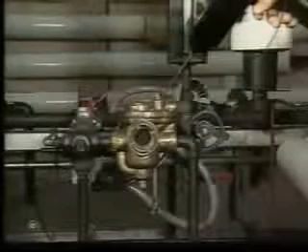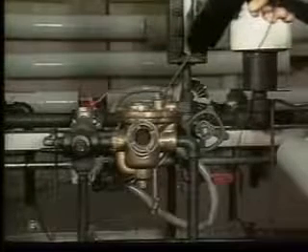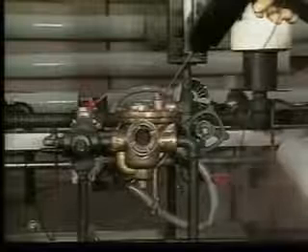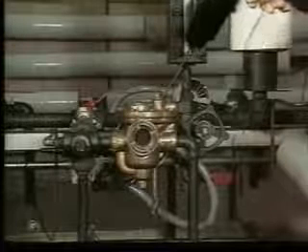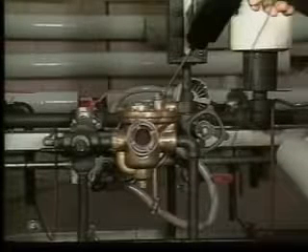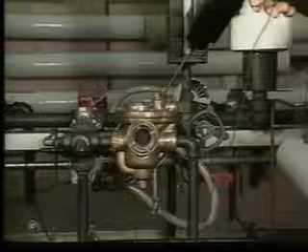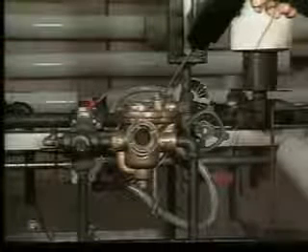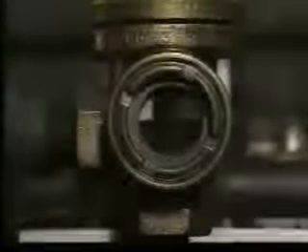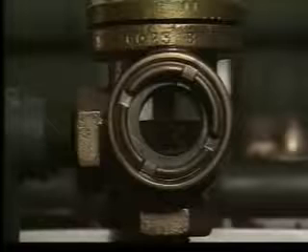Normally, to test the IB trap, touch the downstream side. To hear additional mechanical sounds, touch the linkage. Next, we'll test continuous flow traps.